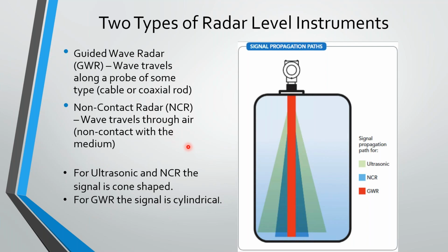Then we have non-contact radar, which we'll also be talking about. The wave travels through the air - nothing comes in contact with the medium. That is more of a cone shape, shown as the darker blue-green area. For comparison, ultrasonic, which has been around a long time, is also cone shaped, but has a much wider beam. Given the same distance and vessel type, non-contact radar will always have a smaller beam than ultrasonic. We'll talk about other things regarding that along the way.